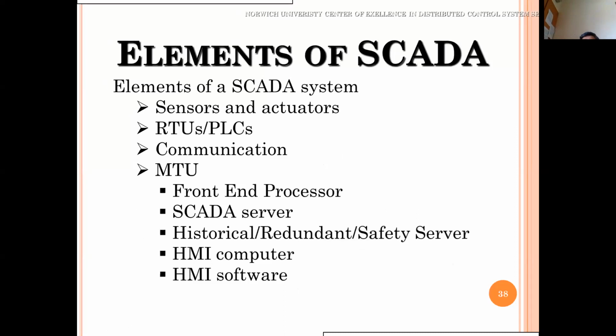And you actually need an HMI, a human machine interface. Actually, before going to the HMI, what is a SCADA? SCADA, you know, is supervisory control and data acquisition. What it does is give the mimic of the plant. Whatever is running in your industry will be graphically represented in the SCADA. Here you have many softwares, such as InTouch by WonderWare, and many other softwares are available.